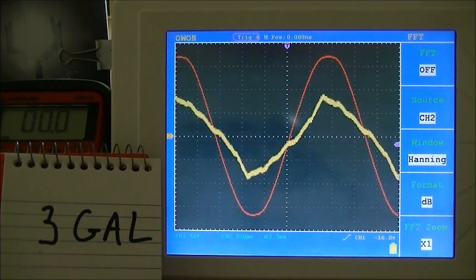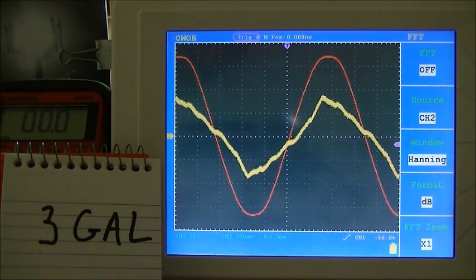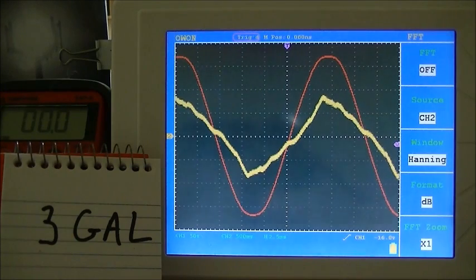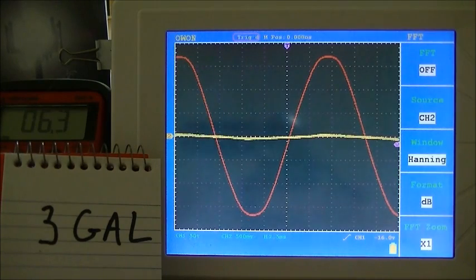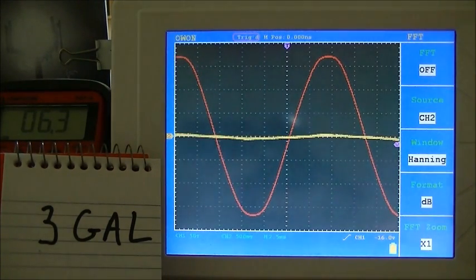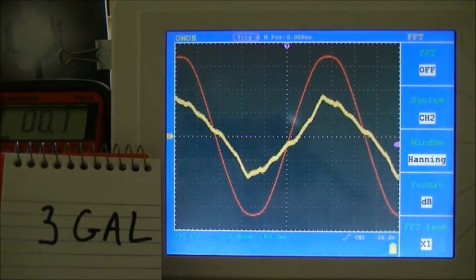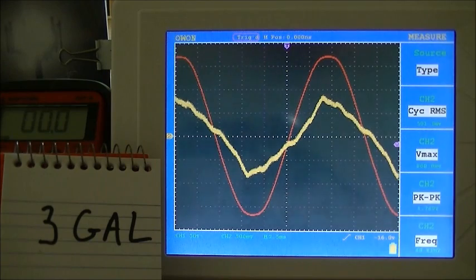One of the last things I want to do is perform a current test. If you watch the meter on the left, I'm going to pass current through that meter from the electrical grounding system to the non-electrified ground rod. Our current availability has gone up a little bit, so we now got 6.3 milliamps. One of the reasons why we're not getting a huge amount of current going between the ground rods right now is that the voltage on the system is quite low. It's kind of a cloudy day today and not many people are running air conditioning systems, and we only have an RMS voltage of 500 millivolts right now.